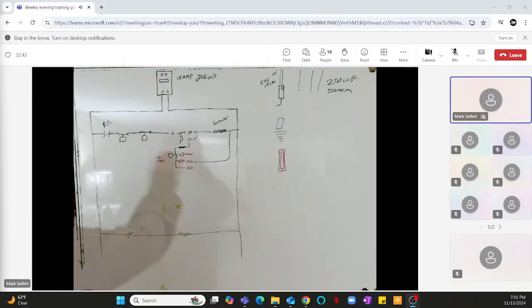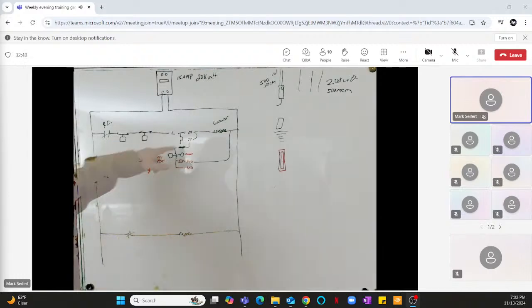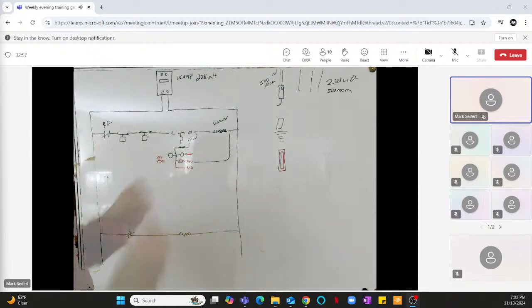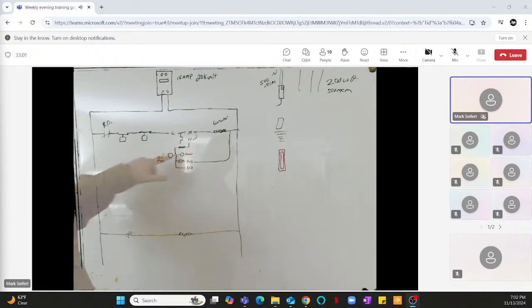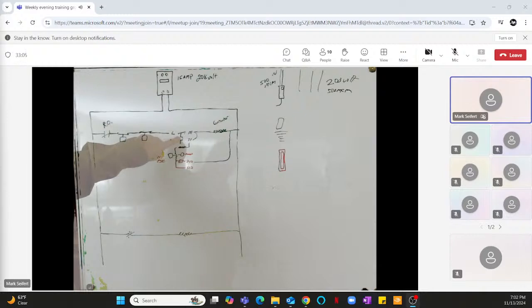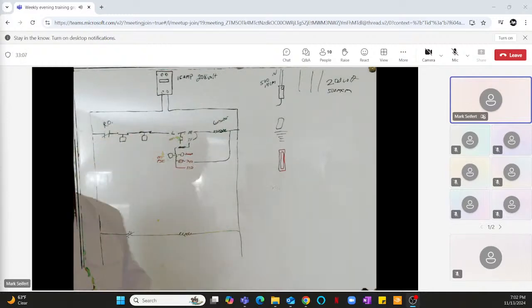It's using Ohm's law, it's using pressure, and it uses the heater as a time delay. That's the time delay right there. You would think right off the bat that it's using the oil pressure as the switch, but it's not. The oil pressure is the switch to kill the heater so it doesn't heat the klixon up high enough to open the circuit.